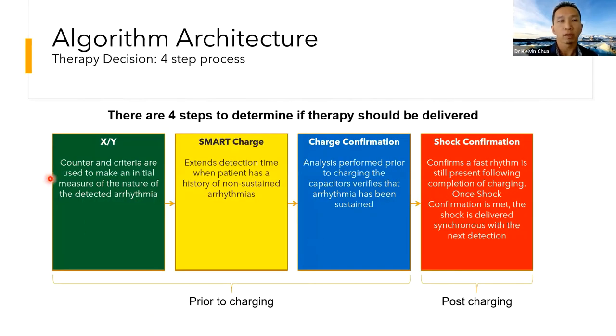X over Y uses a counter and criteria to make an initial measure of the nature of the detected arrhythmia. Smart charge extends detection time when the patient has a history of non-sustained arrhythmias. The analysis is performed prior to charging. The capacitor is verifying the arrhythmia has been sustained before delivering the shock. When confirmation is met, the shock is delivered synchronous with the next detection.